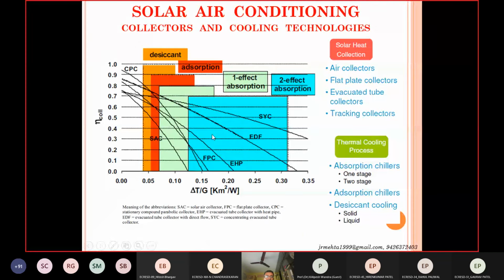So this graph also explains the fact that if you want higher COPs, you have to adopt this area, but in that, for the efficiencies, either you have to go for a better quality solar collector, which would be costlier, or you have to be satisfied with lower efficiency at higher temperatures, right? So there are two considerations. One, whether you want to go for a higher COP of the cooling plant, or you want to go for an economical collector, or there has to be a good combination of these two criteria.